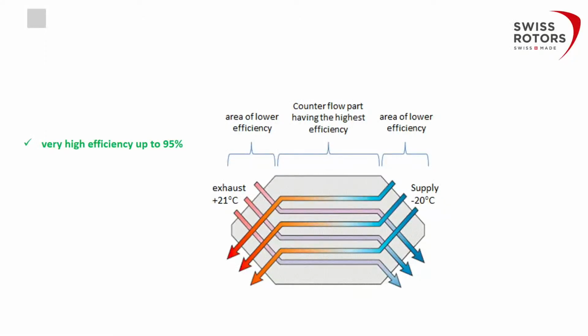So just the basics. Now, why do we have this high efficiency, which can come up to 95%? Because in the middle part, where there is still quite a high temperature difference between supply and exhaust, there is quite a big part of the exchange surface. So you see this middle part, which allows the Counterflow of the supply and the exhaust air, showing these differences.